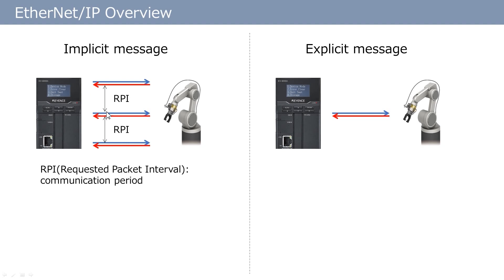With Ethernet IP, a different RPI can be set for each connecting unit. Therefore, you can set a short RPI for units which require high-speed communication such as I/O signals. If speed is not critical, setting a long RPI is also possible.